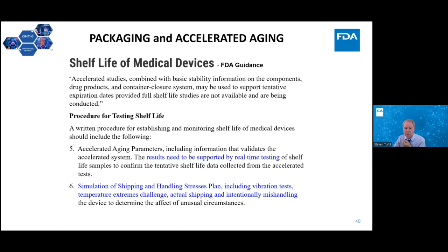So this is for your reference, since I can't directly quote parts of 11607, we incorporated into this our boilerplate deficiency. It's large because it has a lot of guidance in it. Sometimes we don't use the whole thing, of course. If we just need one thing, we'll ask for that one thing. But when it comes to a class 3 device, we might want to see a lot more, or if there's nothing provided in a submission, we may need to give the submitter a lot of guidance. So, all of this text here has to do with what we've already covered: performance testing and stability testing. That's what the first bullet is about.